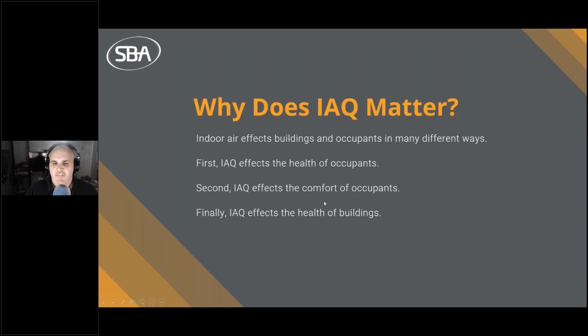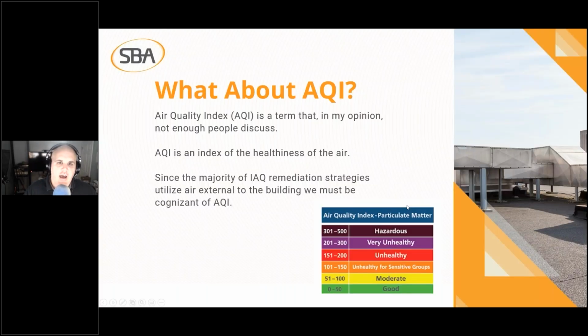And then finally, the health of the building itself. Now, this is why I said some folks will disagree. They will say the health of the building comes before the occupant's comfort, and some folks will say it comes after, like I do. The reason I say it comes after is, yes, you want to make sure you don't have excess humidity so that you have mold buildup. You don't want to run your equipment into the ground by implementing MERV 13 filters, and then the pressure drops so high that your fans are running full speed all the time and you simply are just burning your systems into the ground. That being said, if you have the most perfect, well performing building in the world, it doesn't matter if you don't have people in it. So if you can't get people to come back, that's why I say the comfort of occupants should be our secondary focus of IAQ.